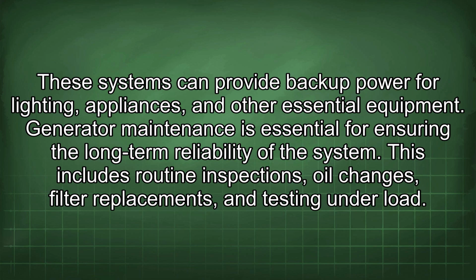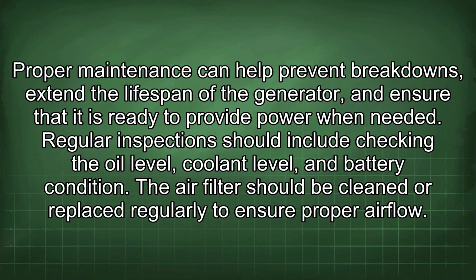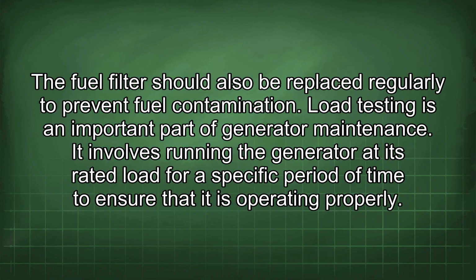Generator maintenance is essential for ensuring the long-term reliability of the system. This includes routine inspections, oil changes, filter replacements, and testing under load. Proper maintenance can help prevent breakdowns, extend the lifespan of the generator, and ensure that it is ready to provide power when needed. Regular inspections should include checking the oil level, coolant level, and battery condition. The air filter should be cleaned or replaced regularly to ensure proper airflow. The fuel filter should also be replaced regularly to prevent fuel contamination.